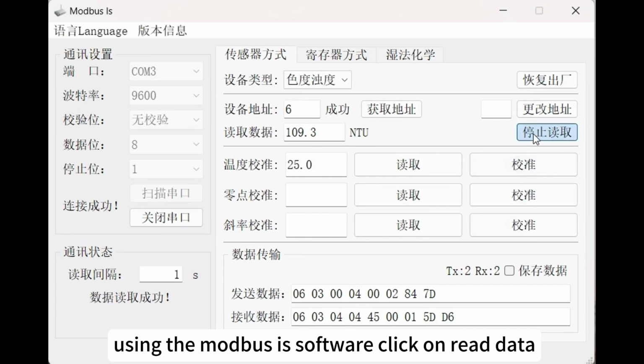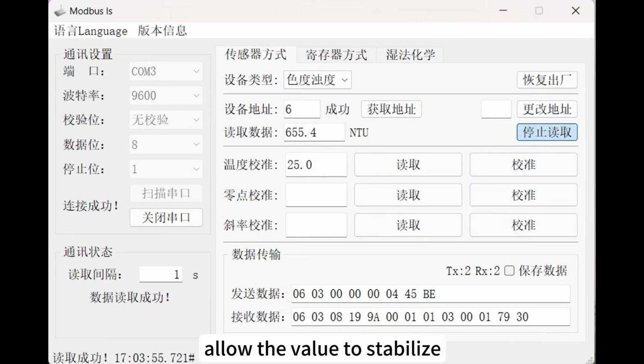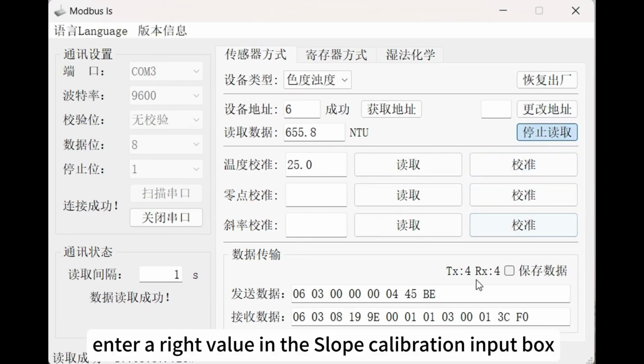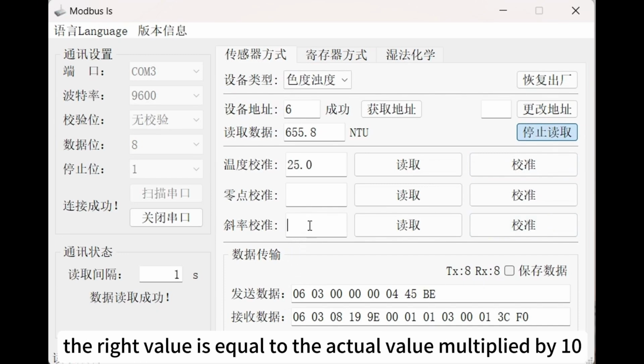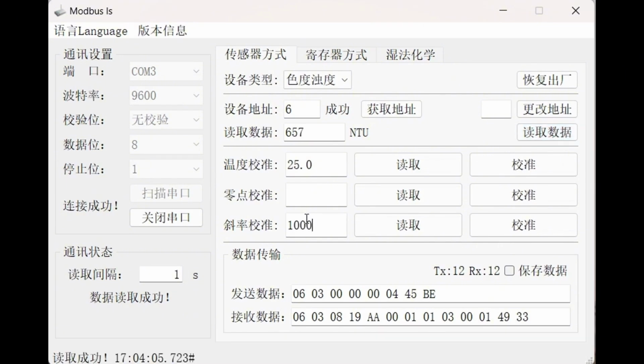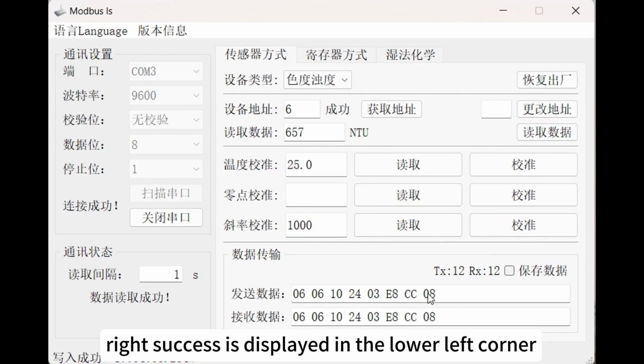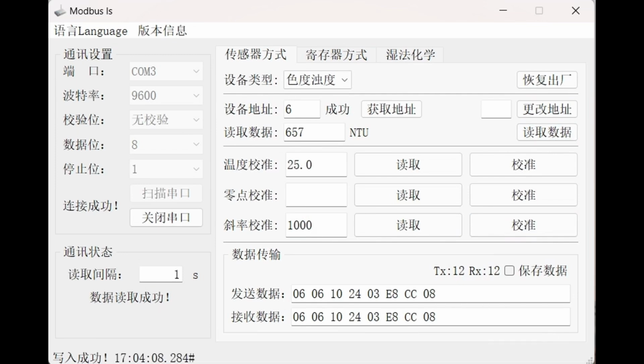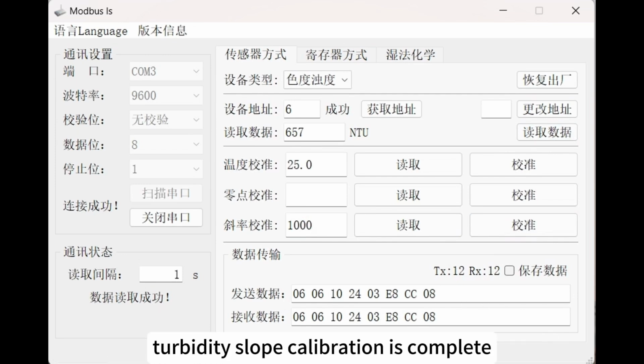Click on Read Data. Allow the value to stabilize. Enter a right value in the slope calibration input box. The right value is equal to the actual value multiplied by 10. Click on Calibrate. Success is displayed in the lower left corner. Turbidity slope calibration is complete.